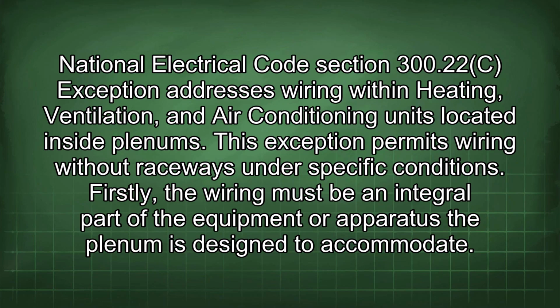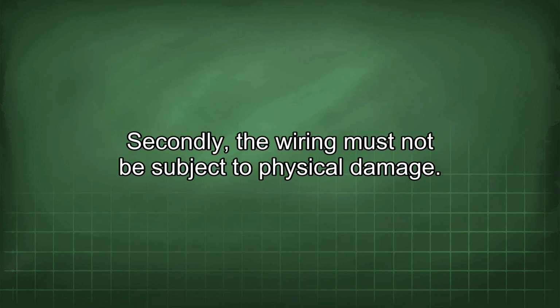National Electrical Code Section 300.22c exception addresses wiring within heating, ventilation, and air conditioning units located inside plenums. This exception permits wiring without raceways under specific conditions. Firstly, the wiring must be an integral part of the equipment or apparatus the plenum is designed to accommodate. Secondly, the wiring must not be subject to physical damage.